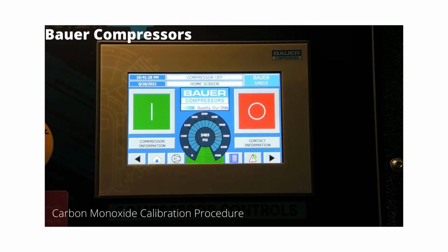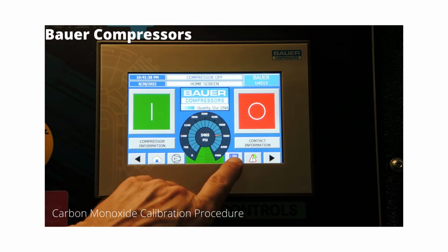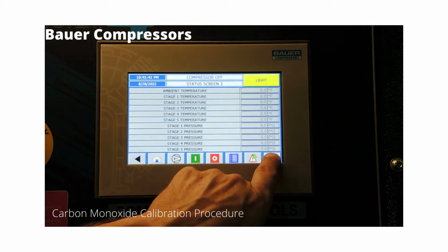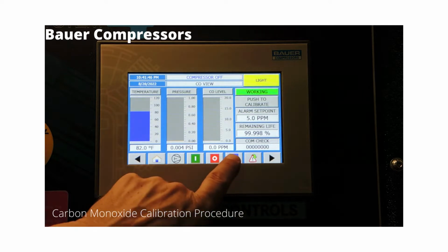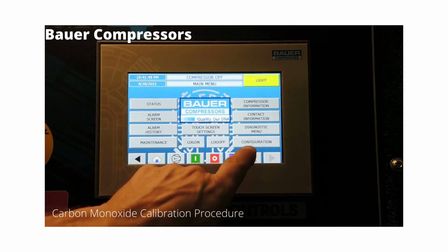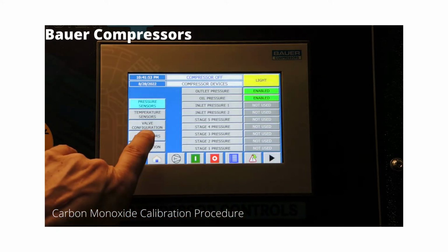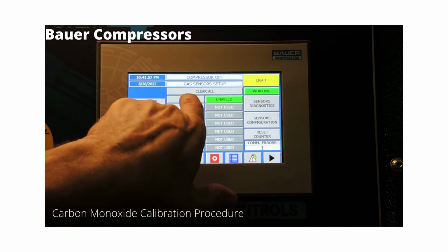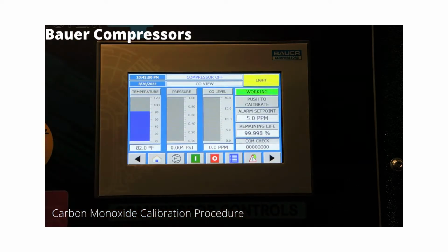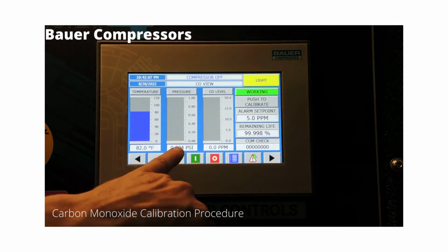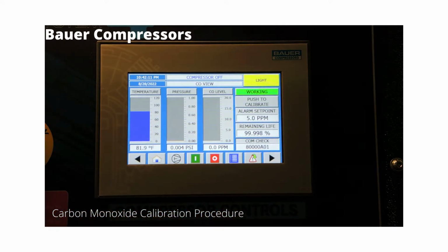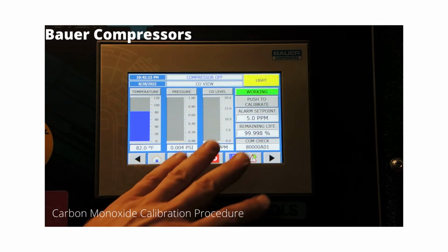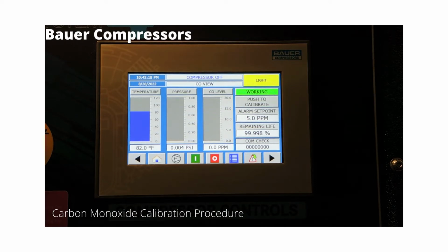Once you've got your test gases, the regulator, you know where the CO monitor is, the compressor's been powered up and everything's been stabilized, you're going to go through a calibration. There's a couple of different ways to find it. You can scroll over here and there's your calibration, or you can go into the menus and go to configuration, device configuration, gas sensors. Here's your CO monitor right there. So there are 2 different ways to find the calibration menu. Right now we can see that it's 82 degrees at the sensor. There's 0 pressure because the compressor is not running. You cannot do the calibration with the compressor running, so make sure it's turned off, and we have 0 parts per million of carbon monoxide.